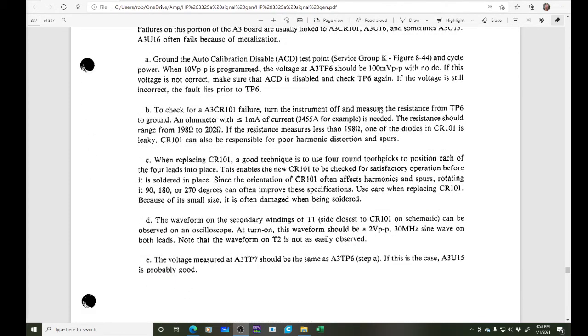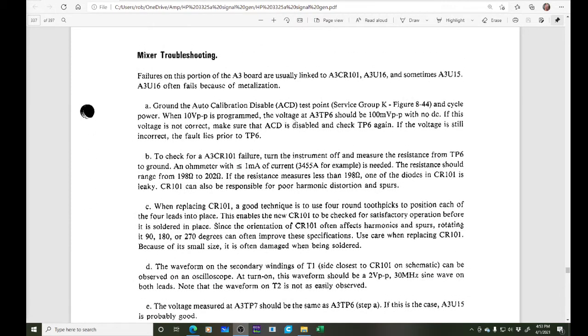Okay, we're back. So we want to ground the auto calibration disable, which we have, and cycle the power, which we have. So when we put 10 volts peak to peak, the voltage at test point 6 should be 100 millivolts peak to peak with no DC. So let's check that.